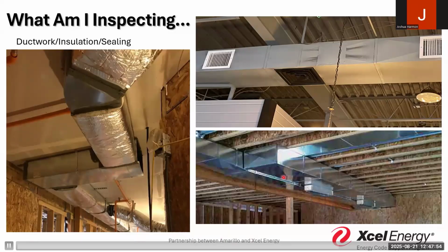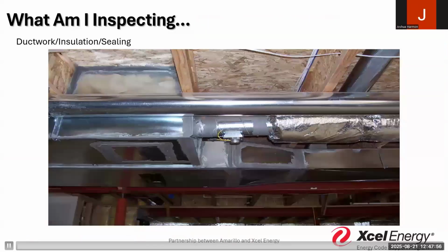Am I looking for square ducts or round ducts? I need to know. This is an example to me of the sealing requirements, and I know this is supposed to be liberally applied. We look at the manufacturer - they say it's supposed to be sealed, taped, or have a liberally applied sealant. This right here is not going to be liberally applied well enough to sustain itself against the airflow movement going through this duct system.